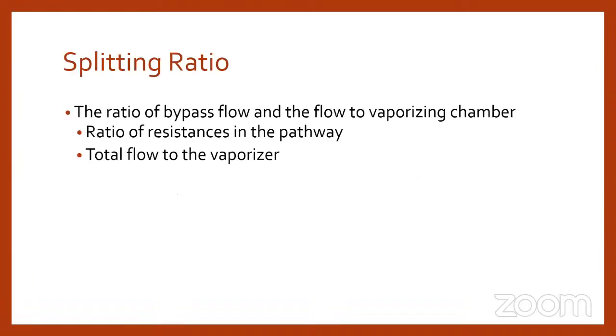Thus, thermostabilization can be achieved while administering anesthesia with these vaporizers. Splitting ratio: the ratio of bypass flow to the flow to the vaporizing chamber is called the splitting ratio. I'll explain the bypass flow in later slides, but this is the basic definition. It depends on two factors. The first is the ratio of the resistance in the pathways. If the resistance is more, the flow in that pathway will be less, and if the resistance is less, the flow in the pathway will be more. The second factor that influences the splitting ratio is the total flow of the vaporizer. If you are using higher flows of fresh gas, then the splitting ratio will vary according to the resistance and other factors.